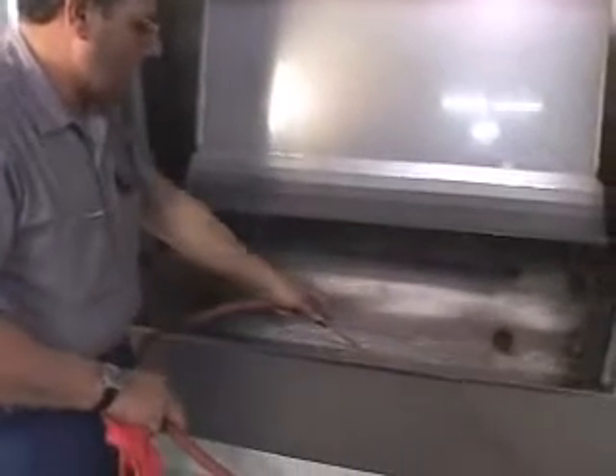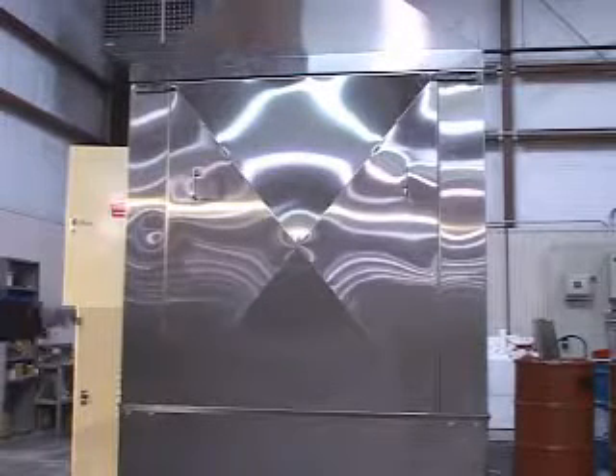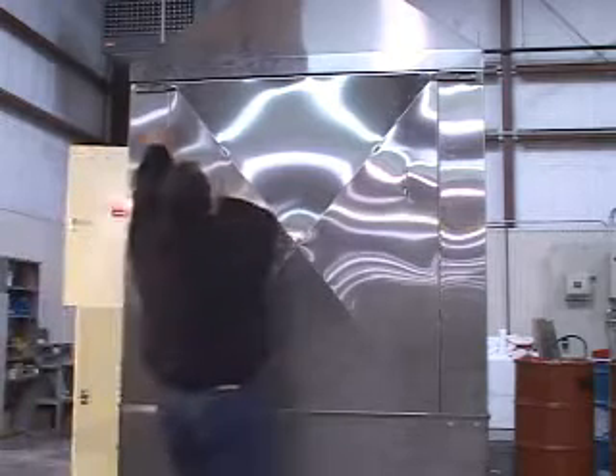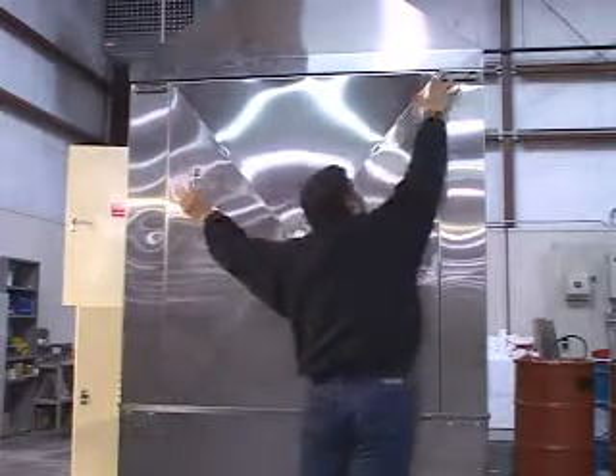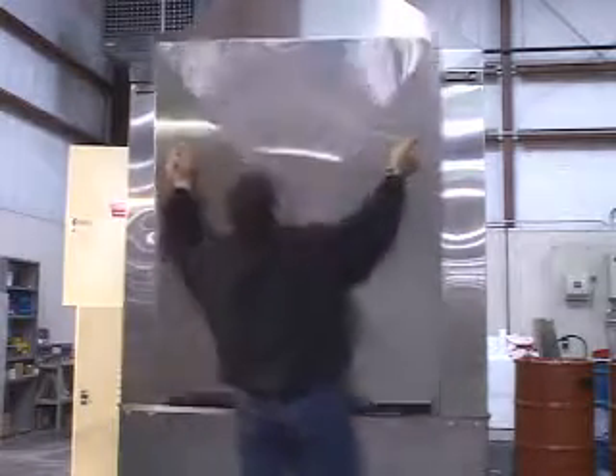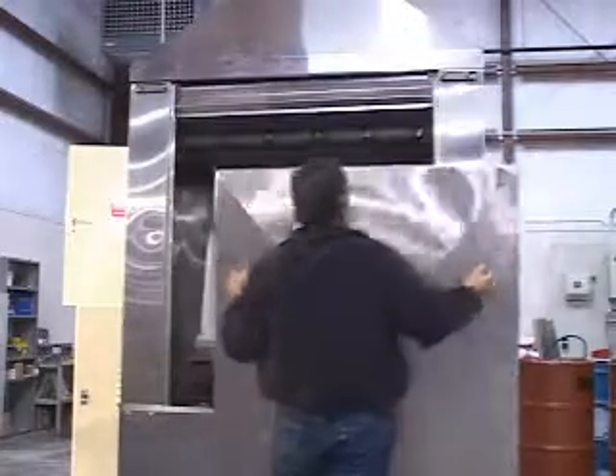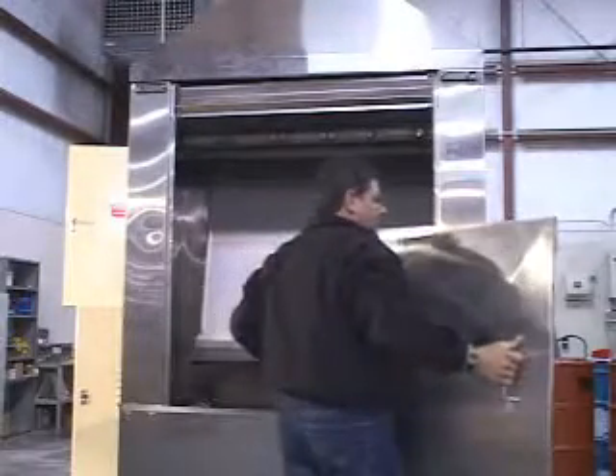Turn off the automatic purging system and run the unit normally for 12 to 24 hours depending on the level of buildup that needs dissolving. When results are satisfactory, thoroughly drain and rinse the tank and spray chamber with fresh water. Turn the purging system back on. Never attempt to open the spray chamber door while the burner is in operation. Opening this door will cause a change in airflow through the unit, redirect the flame to sensitive components, and cause severe damage to the Humidaire unit.